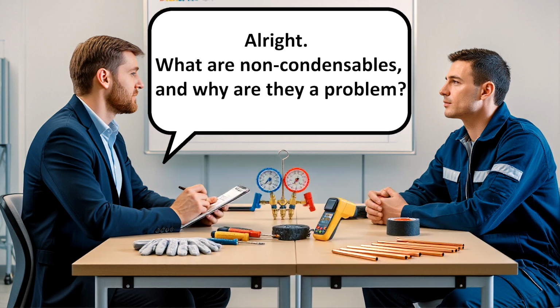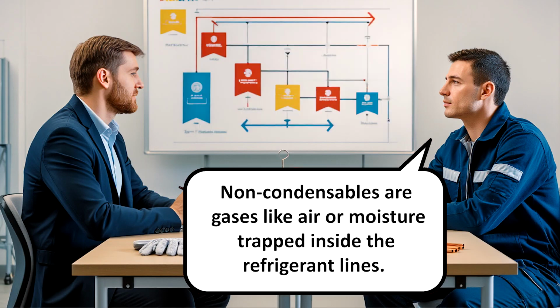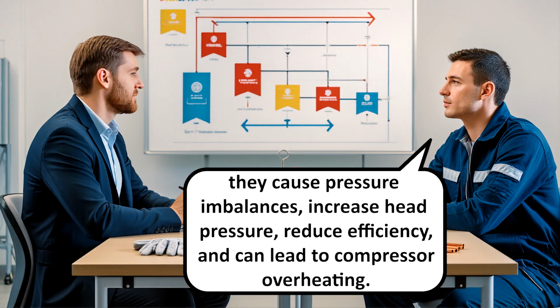All right. What are non-condensables, and why are they a problem? Non-condensables are gases like air or moisture trapped inside the refrigerant lines. They cause pressure imbalances, increase head pressure, reduce efficiency, and can lead to compressor overheating.